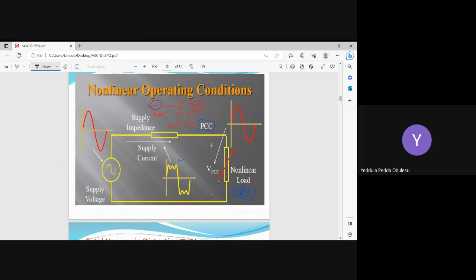If I take this as the source, this is the point of common coupling, the PCC, where more than one load is connected. So many loads are connected like this. Our adjustable speed drive is one of the loads connected at this PCC. This adjustable speed drive is inducing harmonics at the PCC, that means at this supply, so the other loads connected to the same supply are also getting affected. So this problem needs to be eliminated.